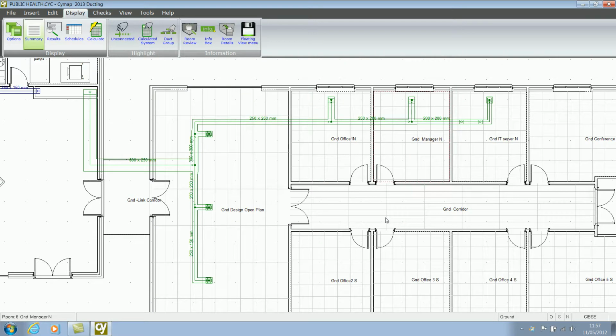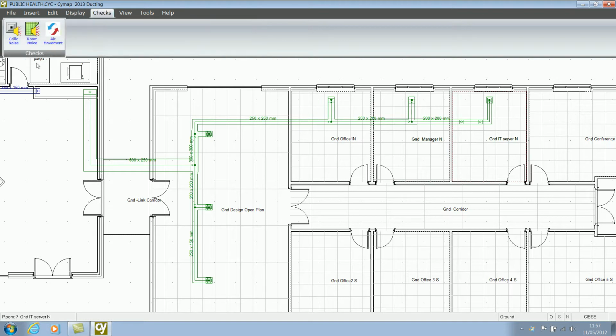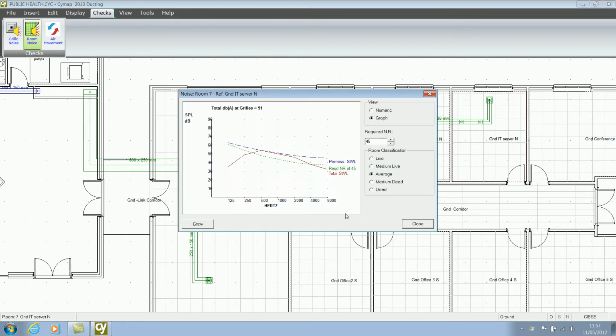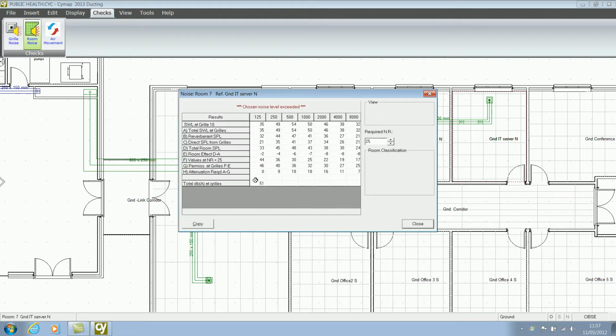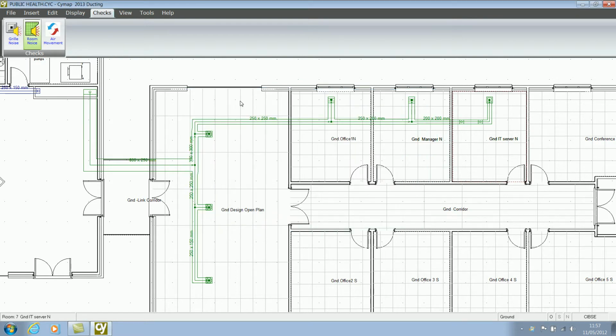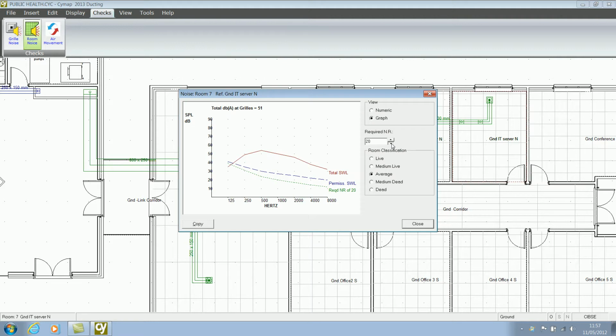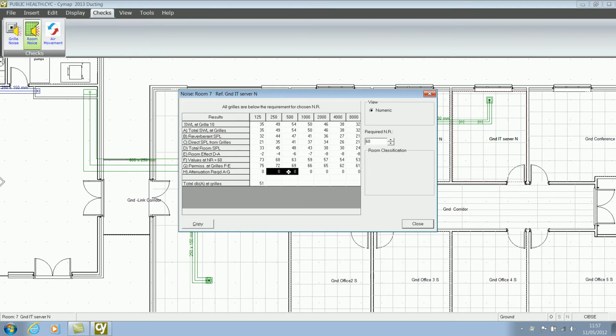If you want to look at a fan noise check or a noise calculation within the space, we can select the room, select the checks ribbon and go to room noise. This gives you, based on the NR rating of the space, any requirement for attenuation. You can see this in the numeric. We would need to attenuate by these frequencies. So you can see here the varying frequencies we'd need to attenuate by various dBA ratings along the bottom line here for a room at an NR of 25. If we're doing a somewhat noisier room, let's say a factory, if we increase the NR rating, then the requirement isn't as stringent, therefore we wouldn't need any attenuation.